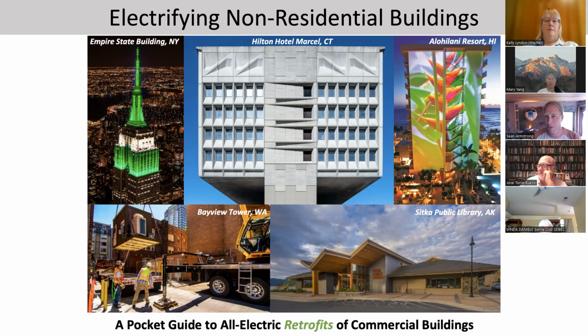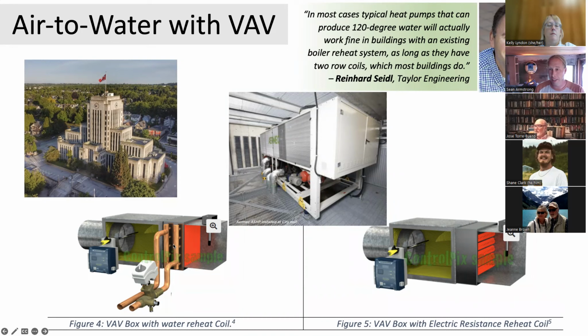Now, what makes the air hot and cold is a choice. Is it water, hot and cold water with the water frequently heated by gas? Or is it electric resistance coils? It turns out that you waste energy even with a heat pump by delivering hot water throughout the entire building during the summer when it's not being used, but that's how the systems are designed. Instead, if you just did electric resistance heaters only when the heat is needed, that actually uses less total energy, just so you know.